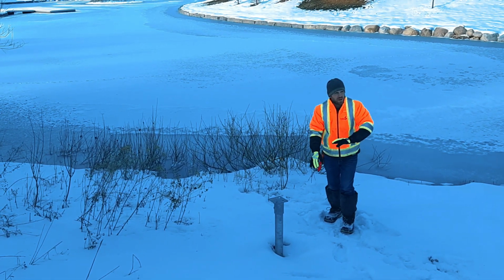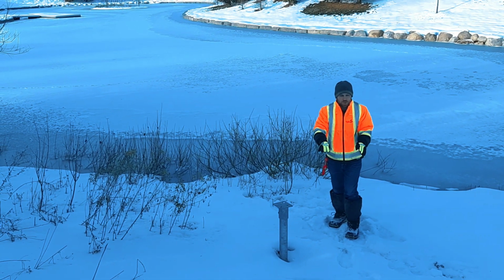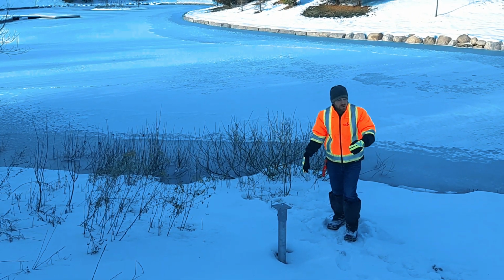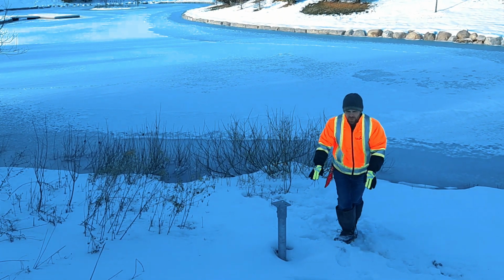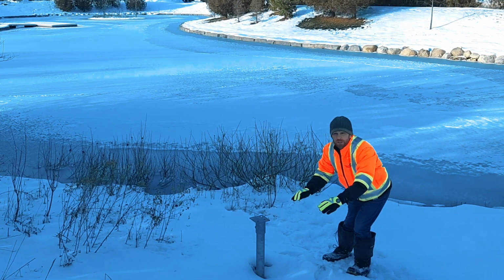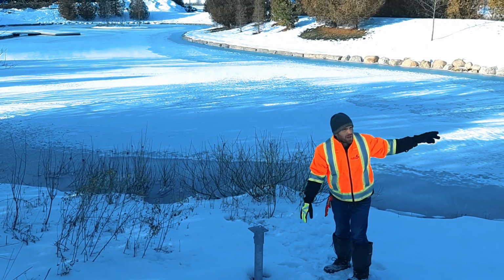Right, so with the check valve it'll all sit in the pipe, and this is all going to be on the backup generator, so it should be okay. But if that would fail, then we're going to be in big trouble. So this way at least the pipe will drain mostly, and it'll be able to get back out. And the only bit of water that could be sitting would be just in the chamber of the pump. So if we have some damage, at least it's 1 pump, 2 pumps, which aren't cheap, but it's a whole lot cheaper than having to deal with it.